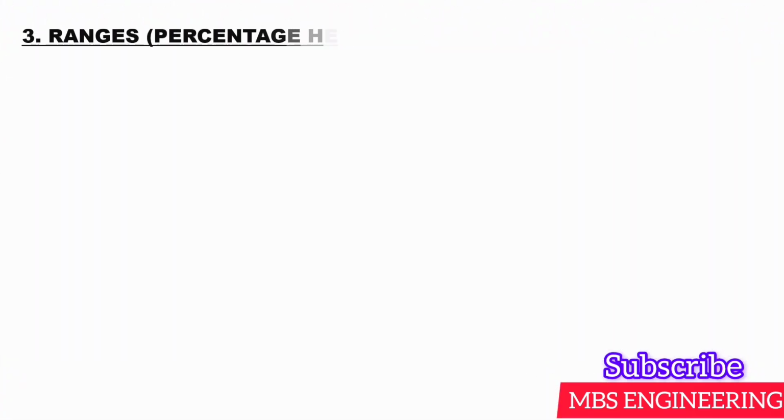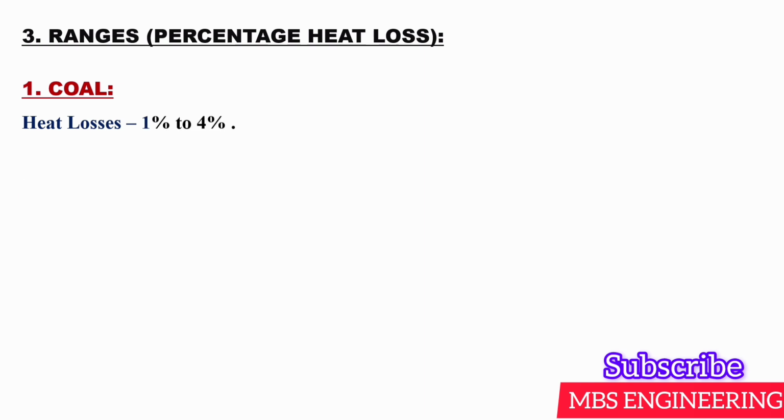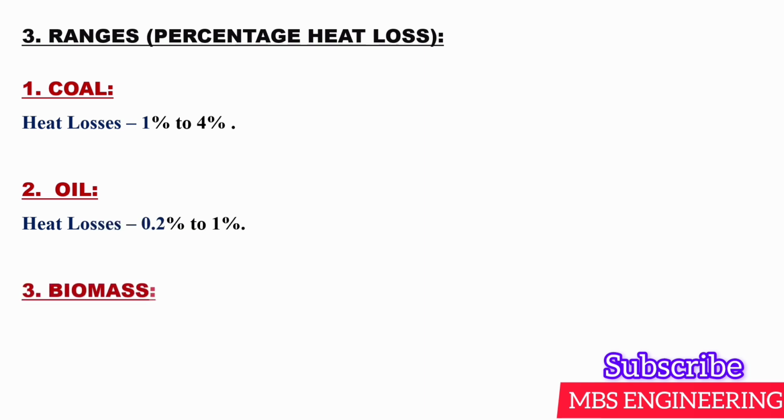Next, we will learn and understand the ranges of percentage heat loss due to incomplete combustion in a boiler. In coal fuel, the percentage of heat loss ranges from 1% to 4%. In oil fuel, it ranges from 0.2% to 1%. In biomass fuel, it ranges from 1% to 3.5%. Even small percentages can cause significant energy loss over time. These losses don't contribute to steam generation but still consume fuel energy.